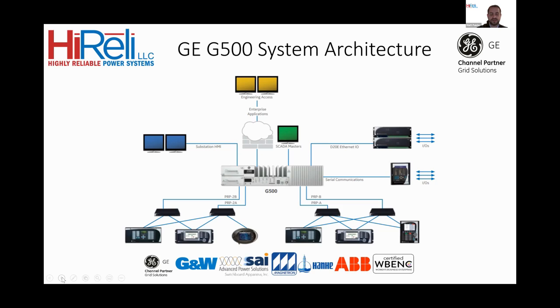Some of the features for the G500 include data collection and visualization, IEC 61850 gateway, device redundancy, file retrieval capabilities. So what that means is if there's a fault in one of your relays, the G500 will pull all the event records and store them in the G500. And there's also built-in HMI.